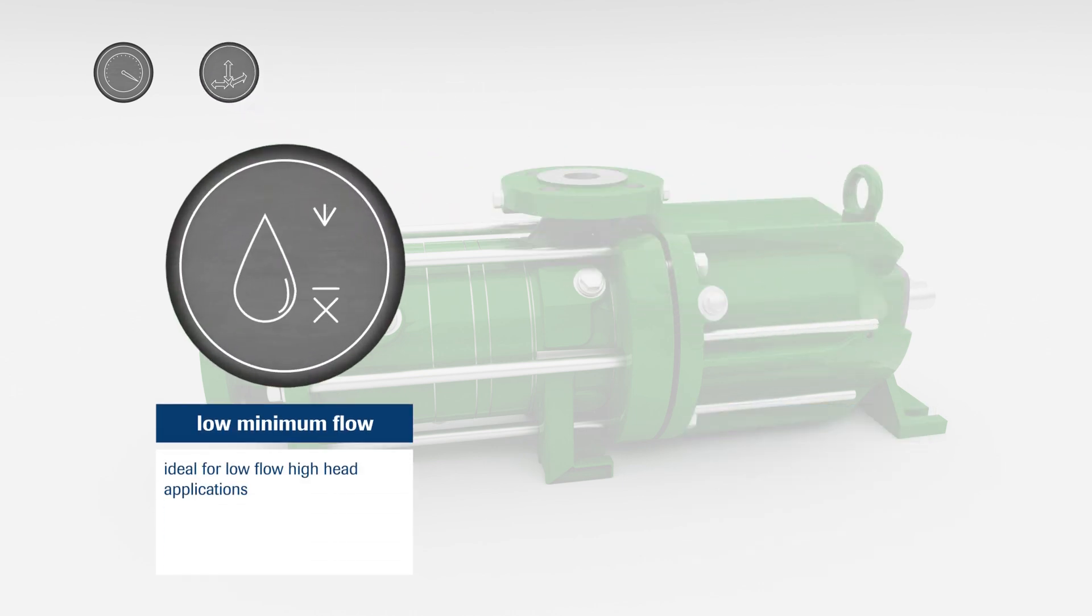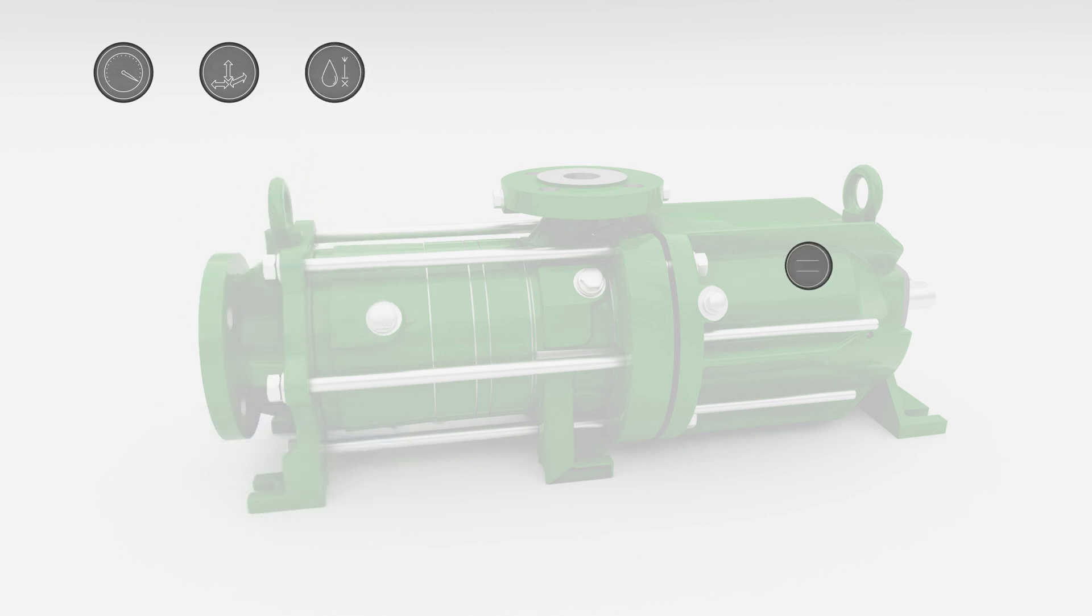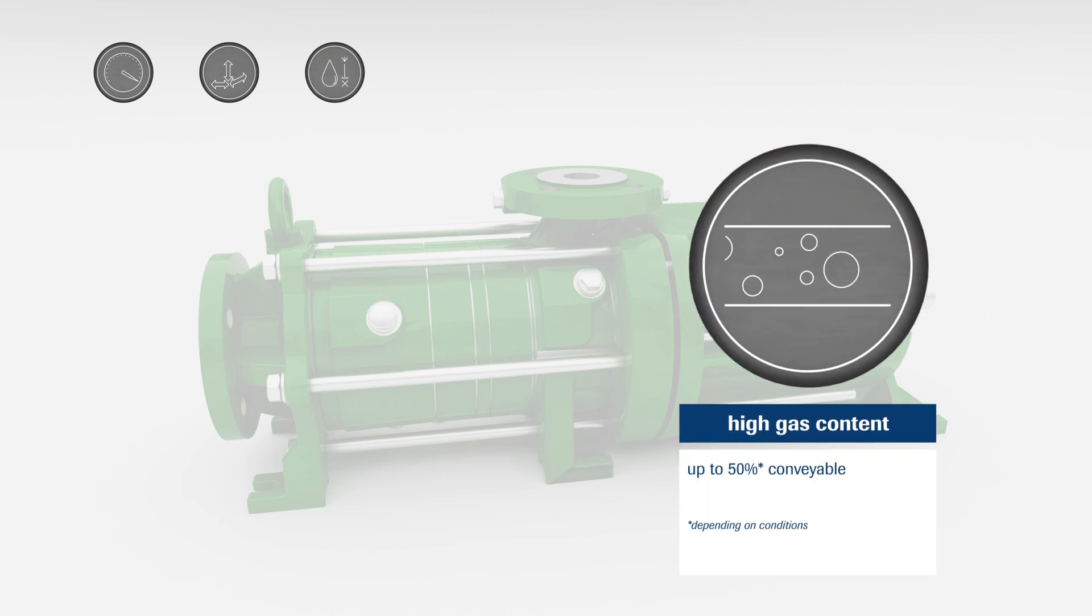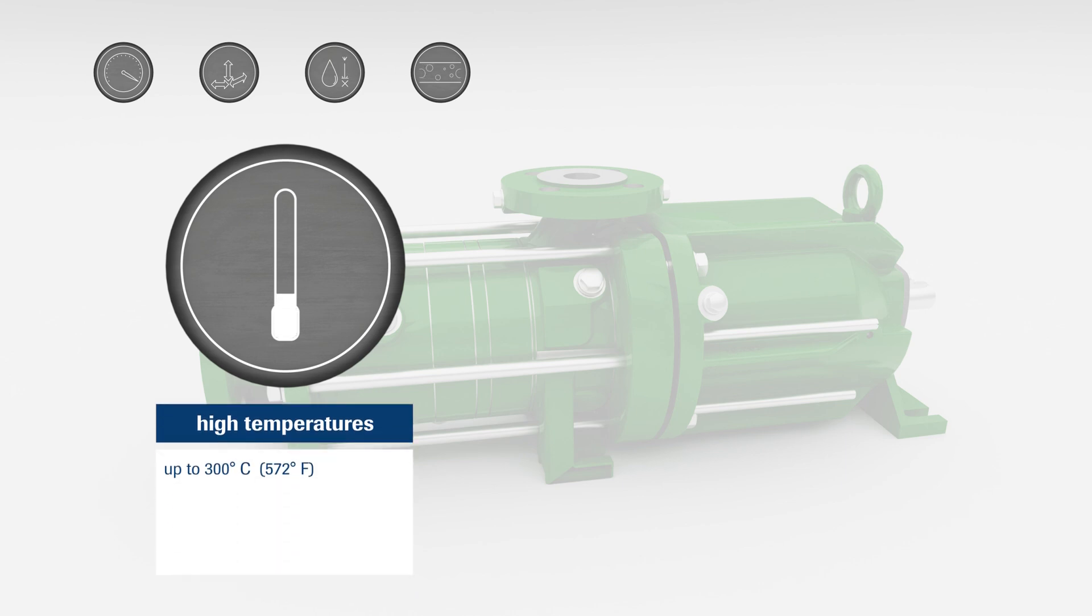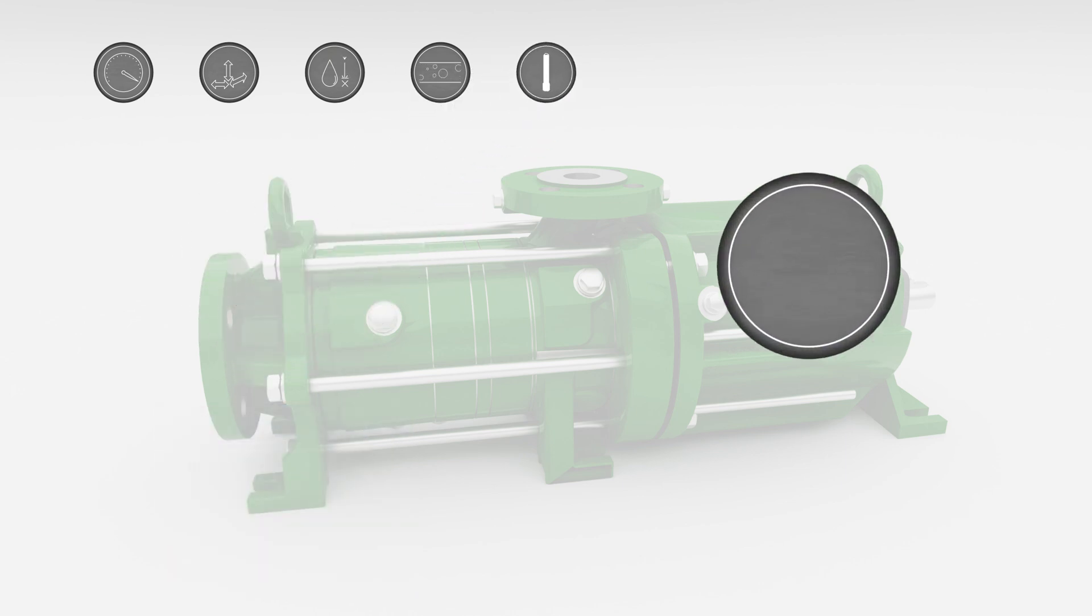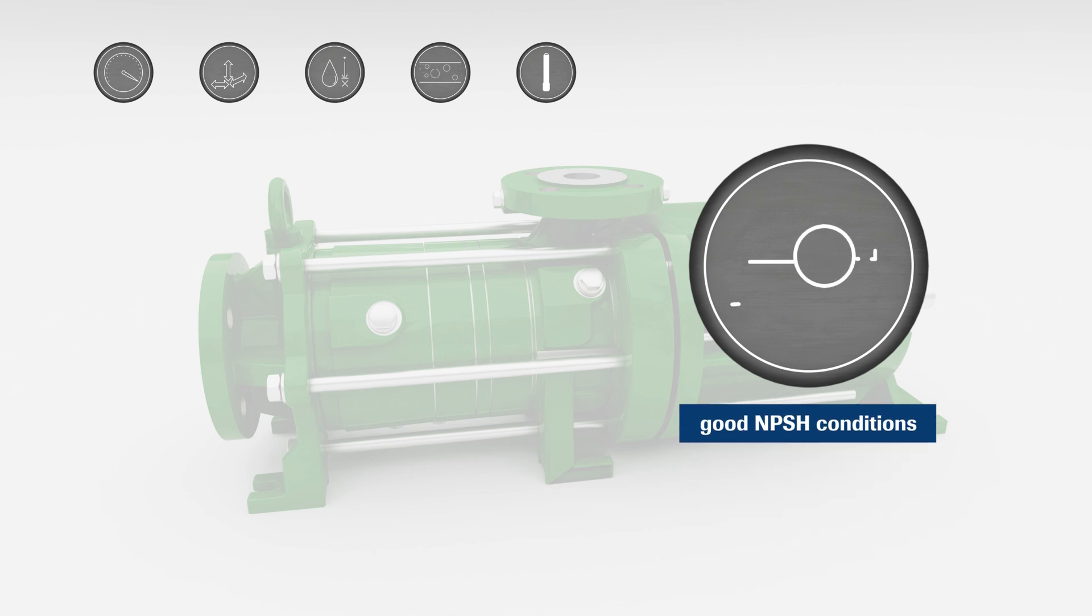Peripheral impeller pumps such as the TPM are ideal for low flow high head applications. Up to 50% gas content can be pumped depending on the conditions. High temperature applications up to 300 degrees centigrade are possible. Good NPSH properties are possible thanks to suction impeller and axial inlet.